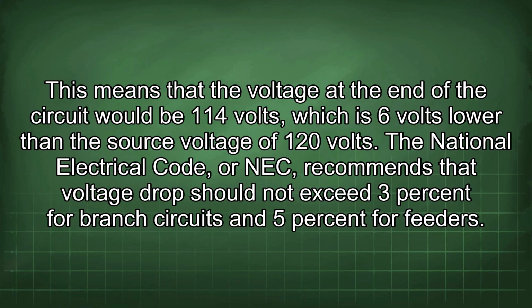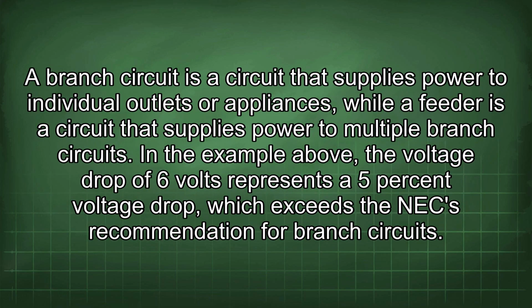The National Electrical Code (NEC) recommends that voltage drop should not exceed 3% for branch circuits and 5% for feeders. A branch circuit is a circuit that supplies power to individual outlets or appliances, while a feeder is a circuit that supplies power to multiple branch circuits.